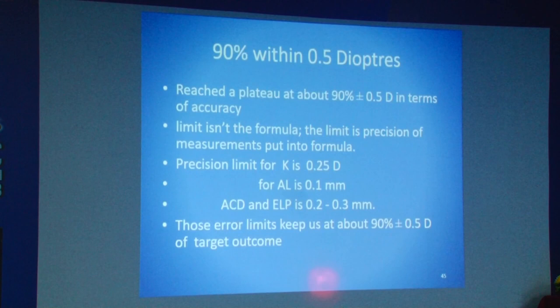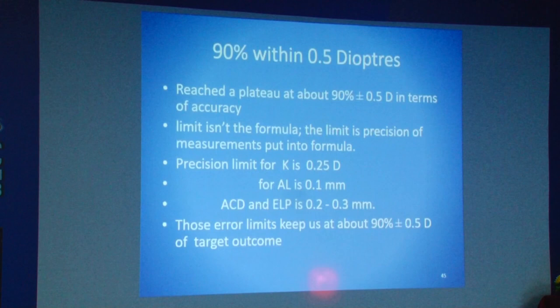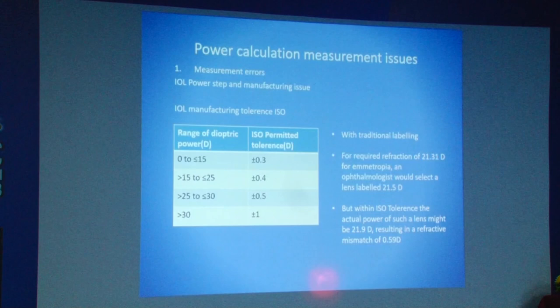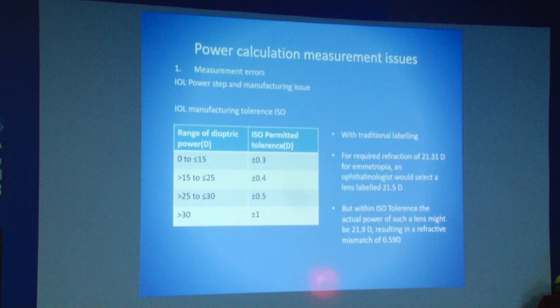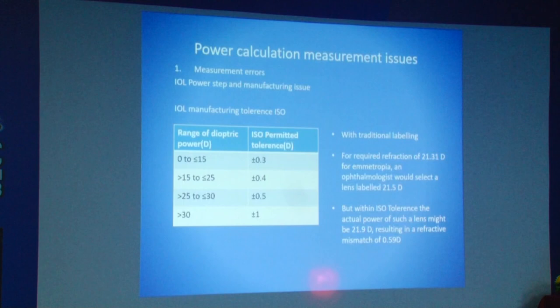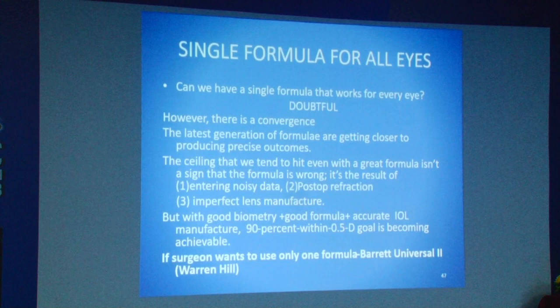Why are we still stuck at 90% accuracy within 0.5 diopters? The limit is now not the formula — we have very good formulas. The limit is the precision limit for keratometry, where the least count is 0.25 diopters; for axial length it is 0.1 mm; and for anterior chamber depth it is 0.2 mm. These least-count error limits keep us at 90% accuracy. Additionally, there is ISO permitted tolerance for various powers — if I calculate 21.3 diopters, the nearest available power is 21.5, and with an ISO tolerance of 0.4, the effective power could be 21.9 diopters — a 0.6 diopter error even with perfect calculation, good instruments, and good surgery. This error is beyond our control.